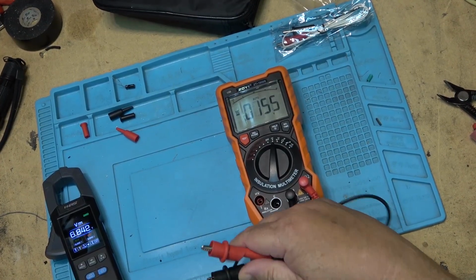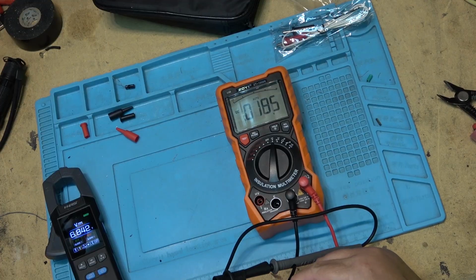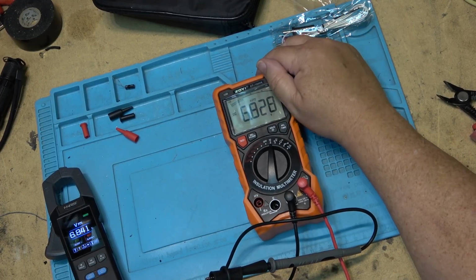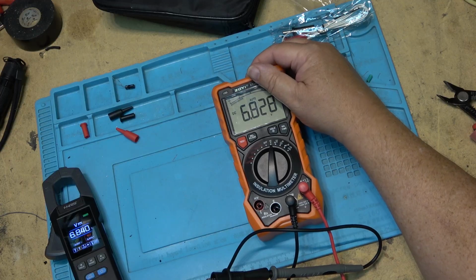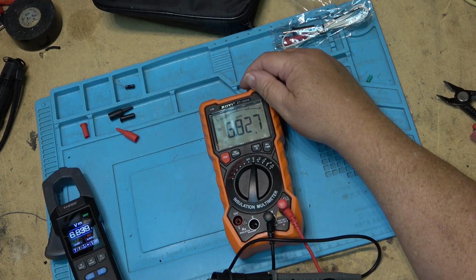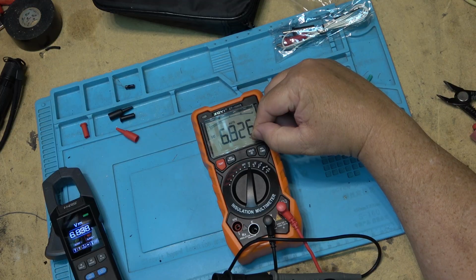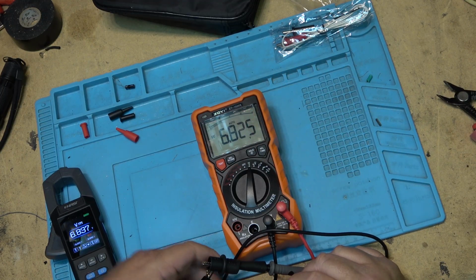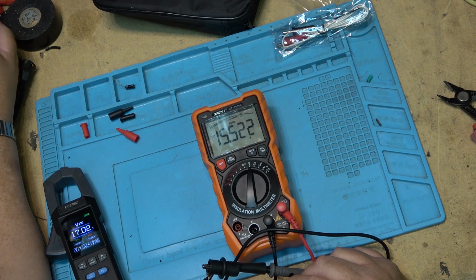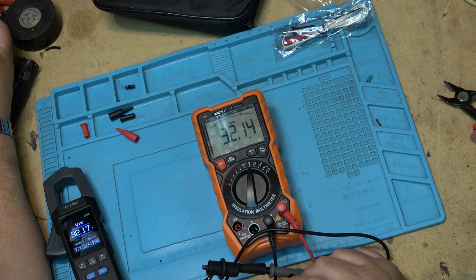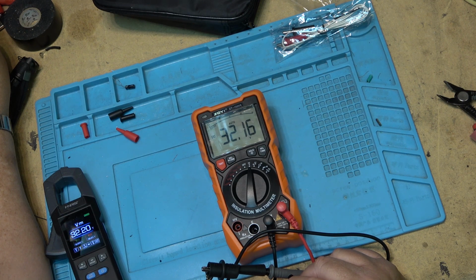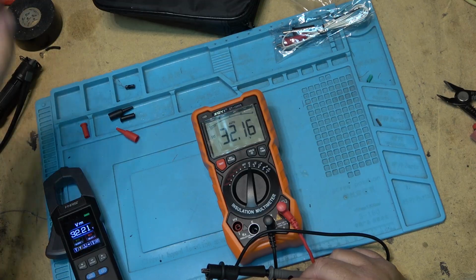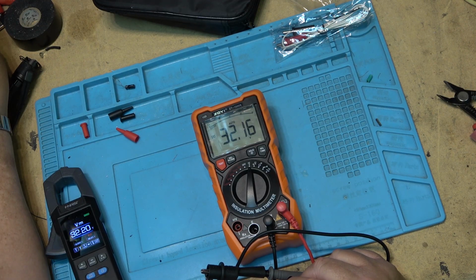I'll just clip it on. My other meter's on there now. 6.84 volts is what the power supply is set for, and this one's saying 6.828, so close. 6.839, 6.826, so it's fairly close. As I raise and lower the voltage on the power supply, we'll take it up to the maximum. 32.19, 32.15. So it's off by a little bit. The reading is slightly low, 4 hundredths of a volt low. And I know this one's accurate because my Fluke tracks exactly.